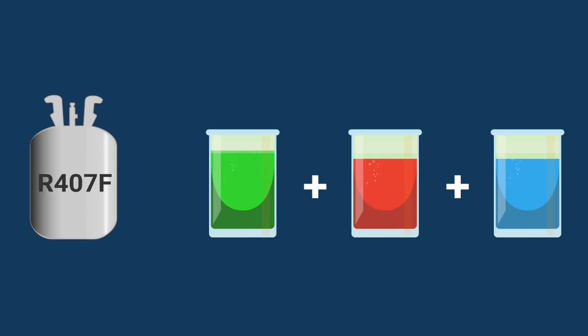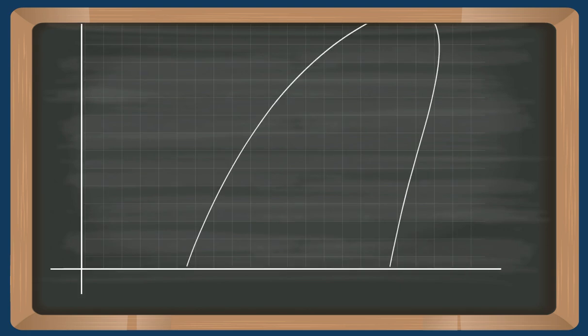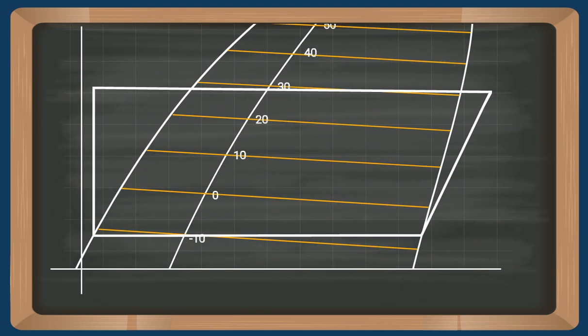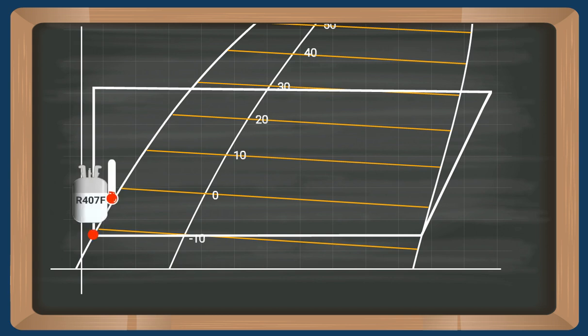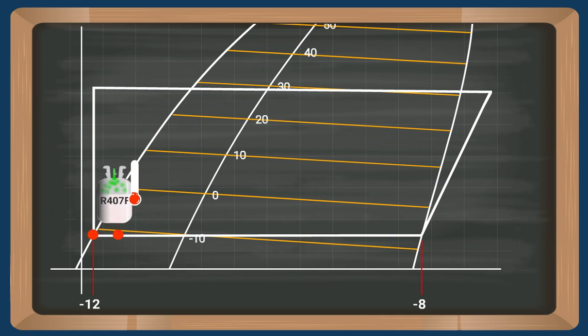If we look at the HLogP diagram for R407F, you'll see that the temperature curves decline to the right. This means that the evaporation will start at a lower temperature here, minus 12 degrees Celsius. This is because the R32 component will start boiling before the other two ingredients.